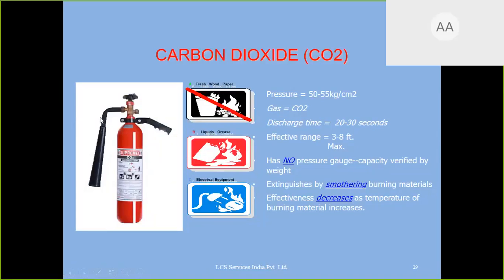Right? So CO2 gas, when it is there, by putting more and more CO2, it creates a deficiency of oxygen and controls the fire. The pressure of CO2 is 50 to 55 kg. It is very, very high compared to DCP. DCP has 15 kg, this has 50 kg. Gas CO2, discharge time 20 seconds, effective range is 3 to 8 feet, and it has no pressure gauge.